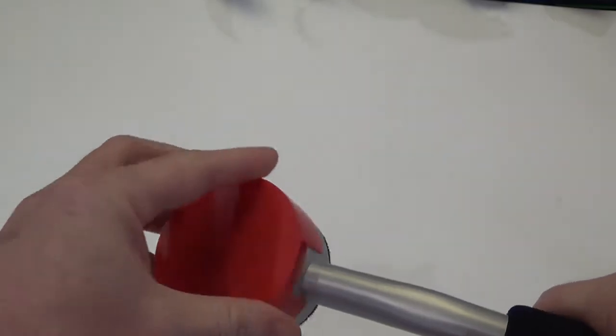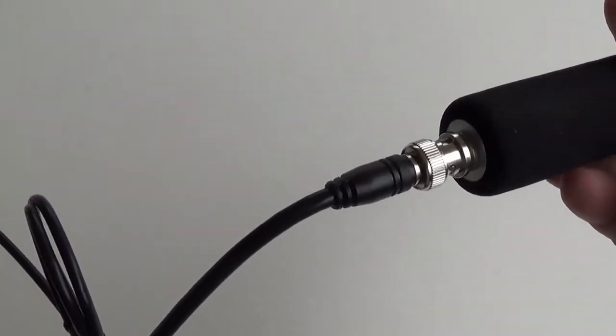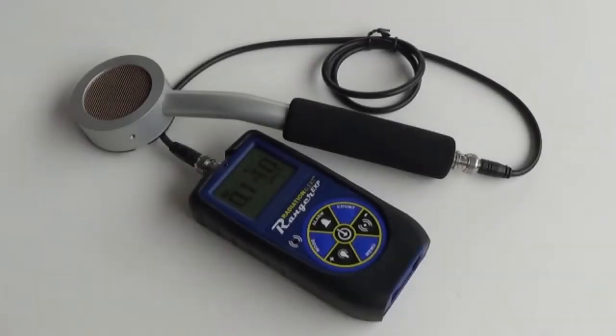The external GM detector has a 2-inch end window located under the protective tube cap. If you need to disconnect the external GM probe, be sure to turn off the Ranger EXP before disconnecting the BNC cable.